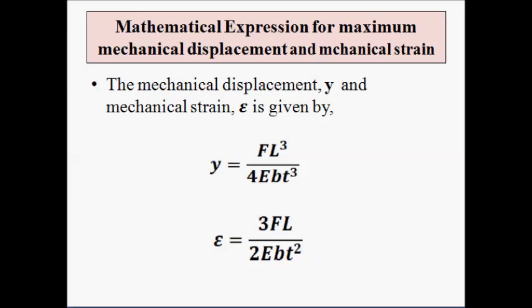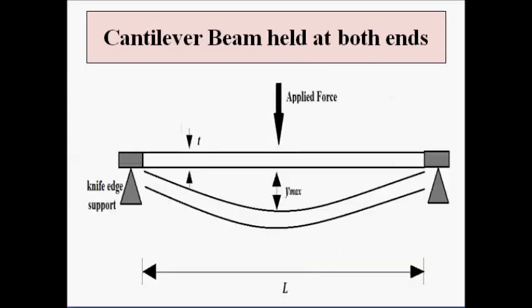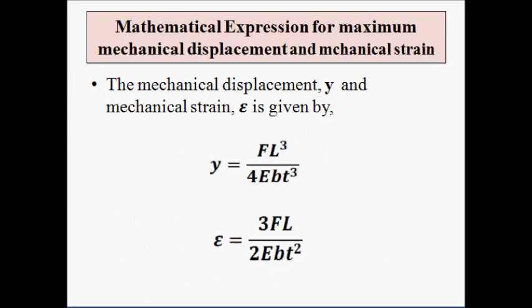We have discussed the cantilever beam for measurement of force or weight in both configurations — the beam held at one end, and the beam held at both ends. In both cases, there is a direct relationship between the displacement produced and the force applied, and between the mechanical strain induced in the beam and the applied force. This can be used to construct a graduated and calibrated scale so that we get an output in terms of force values directly related to either mechanical displacement or strain.